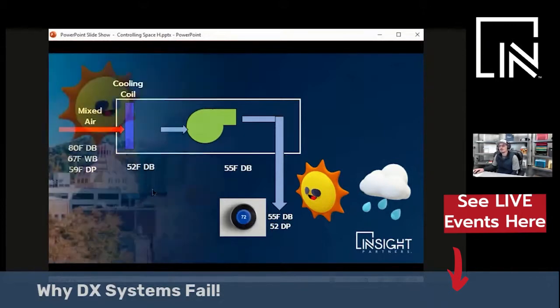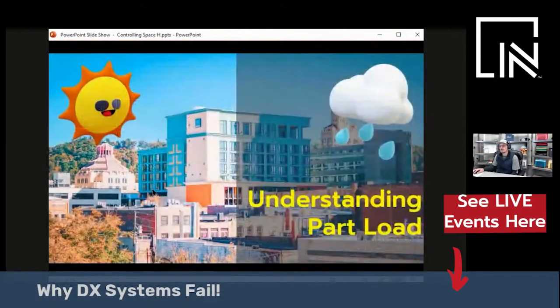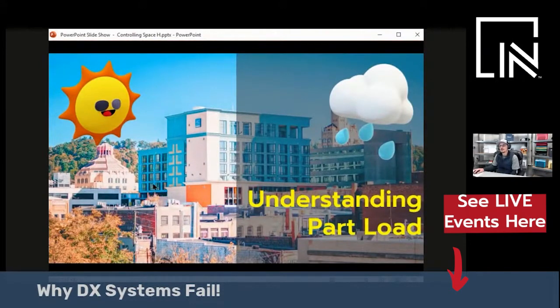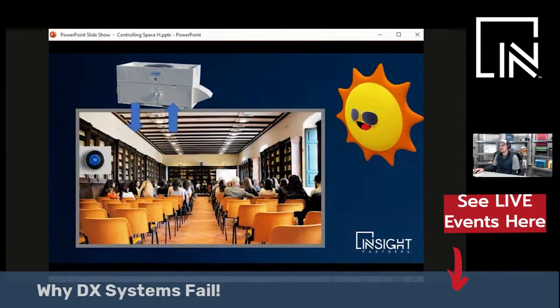And therein lies the problem with controlling humidity at all load conditions. To understand this scenario, you just have to understand part-load. So very briefly, systems are typically designed for full-load days. It's the middle of the summer. It's hot out. The sun's shining in all the windows. You have a bunch of people in the space. You want very cold air in that space.